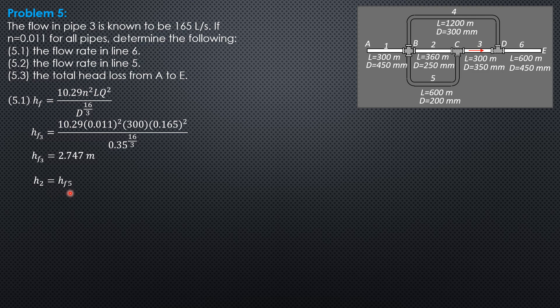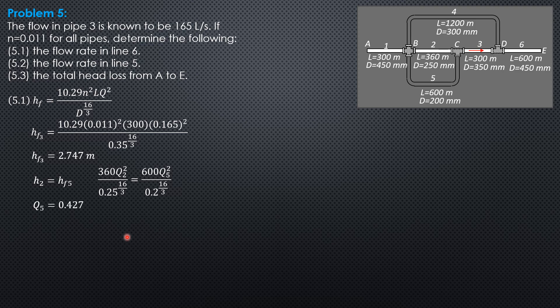Then HF2 equals HF5. Since 10.29 and N² are common, they cancel out. Proceeding with length times Q² over diameter to the 16/3: 360 Q2² over 0.25 raised to 16/3 equals 600 Q5² over 0.2 to the 16/3. Expressing Q5 in terms of Q2 gives Q5 equals 0.4272 Q2.